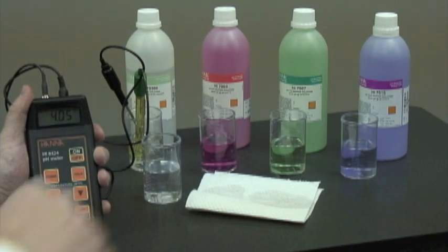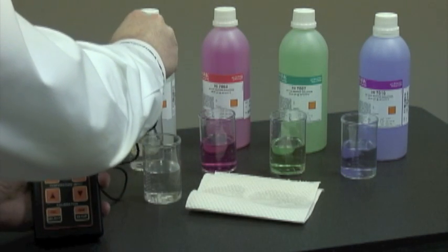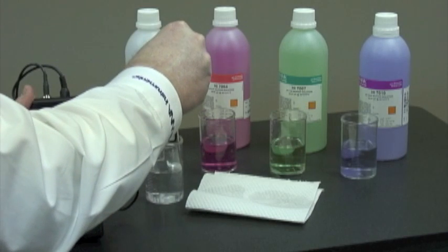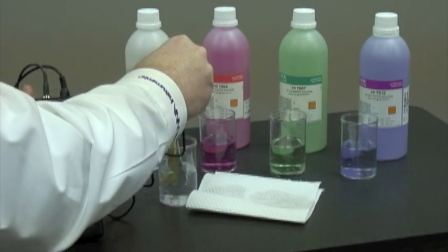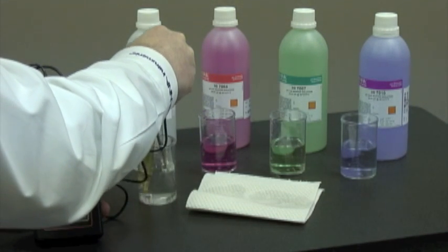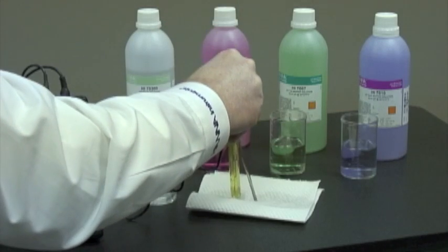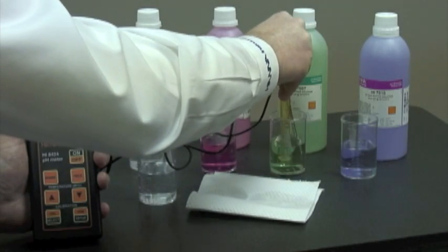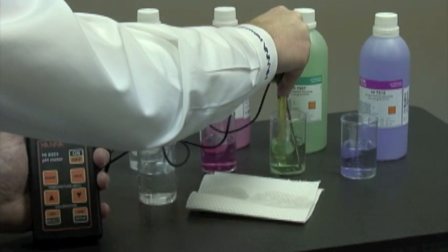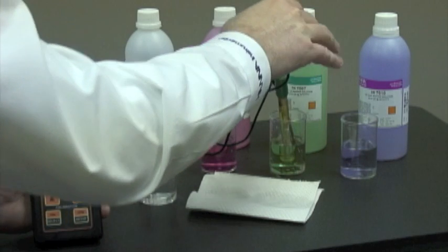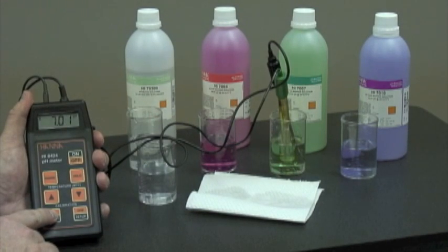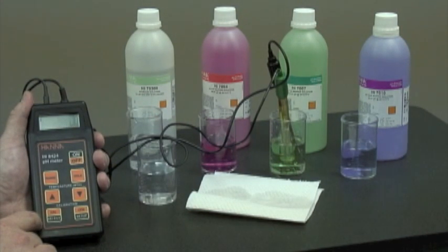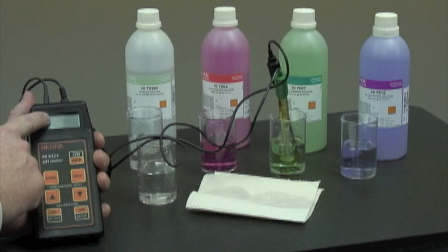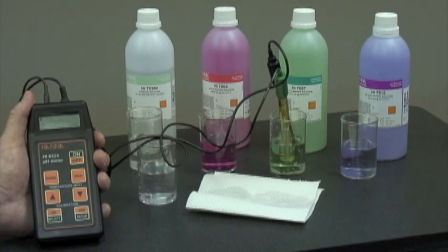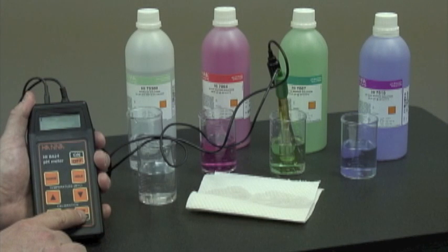Now that 2 hours has passed, we'll rinse the probe with some purified water and place it in the pH 7 buffer. We'll hit the calibration key and we'll wait for a CFM to show up on the display. Once we see that and it beeps, we'll hit the confirmation button.